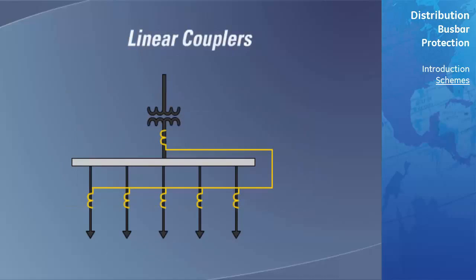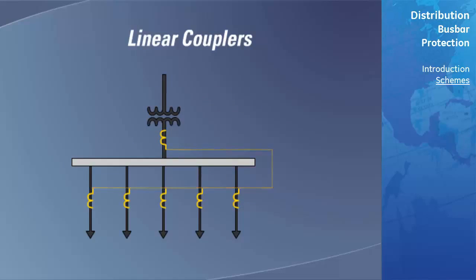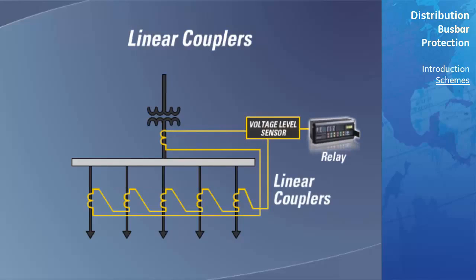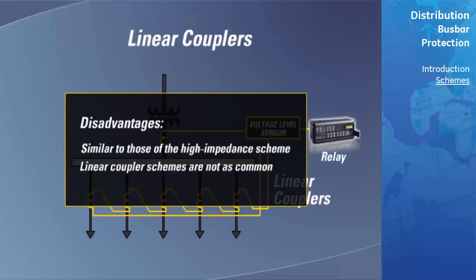A linear coupler, or air-core mutual reactor, produces an output voltage proportional to the derivative of the input current. Because they are using air cores, linear couplers do not saturate. During internal faults, the sum of the bus bar currents, and thus their derivatives, is zero. Based on this, a simple bus bar protection scheme is achieved by connecting the secondary windings of the linear couplers in series, in order to respond to the sum of the primary currents, and connecting a simple voltage sensor to either end. The disadvantages of this approach are similar to those of the high impedance scheme, in addition to the fact that linear coupler schemes are not as common.